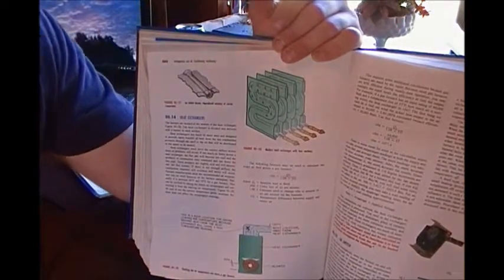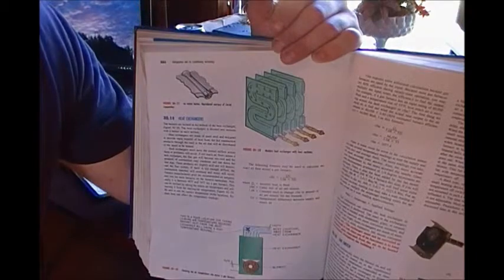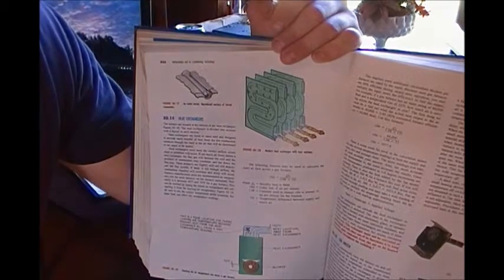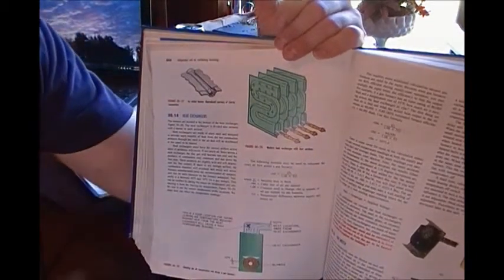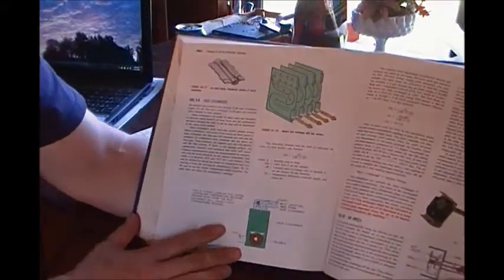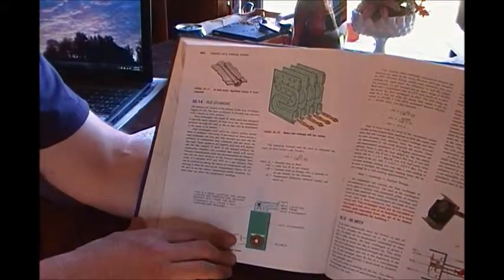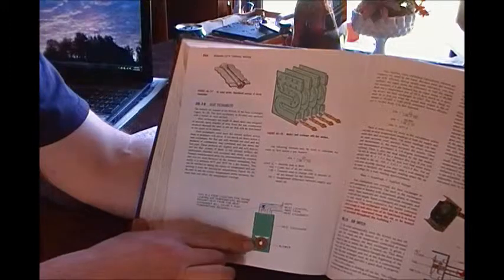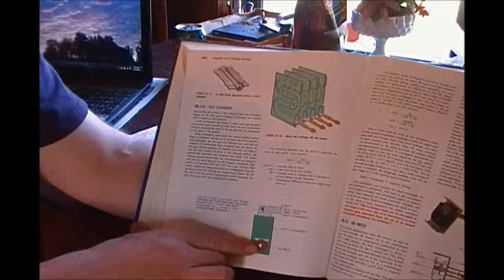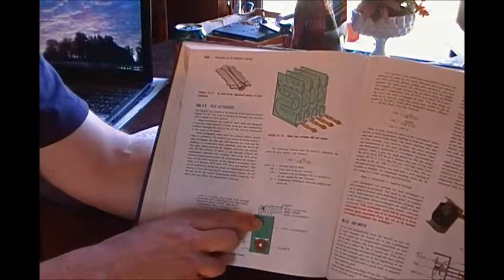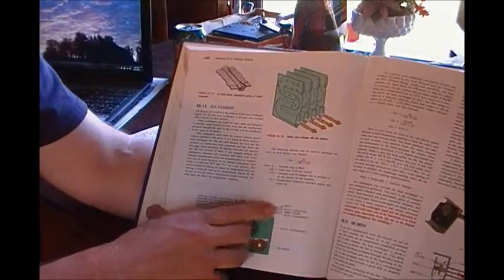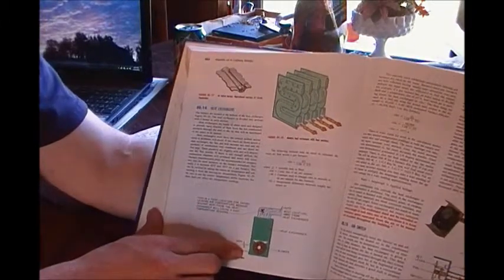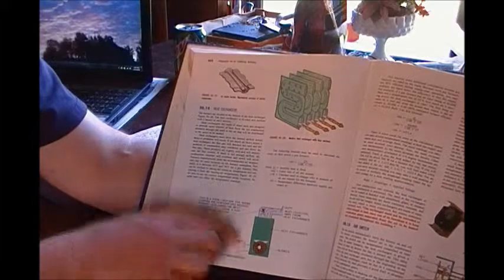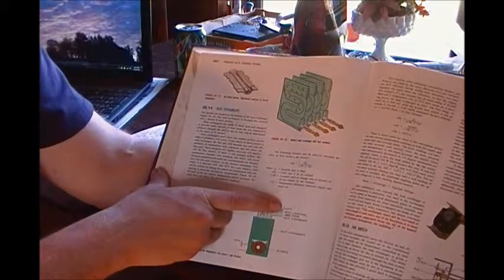Okay, now let's say you've already checked your gas valve pressure, you've installed the furnace, you're running it, and you're balancing it. What you have to do is take a thermometer and put it down here at the bottom, at the return air going into the furnace, and then the air is pulled across the exchanger, heated, and thrown out the top. What's important to know here is that you have 75 going in and 130 coming out.